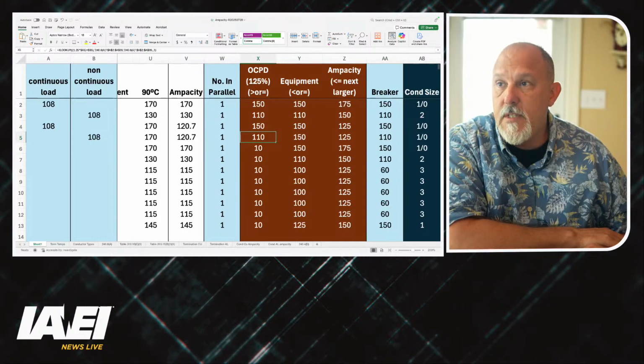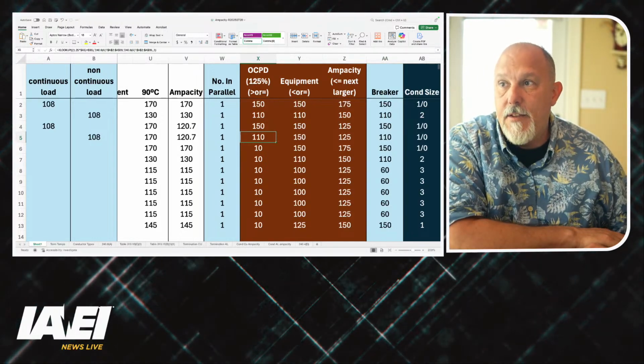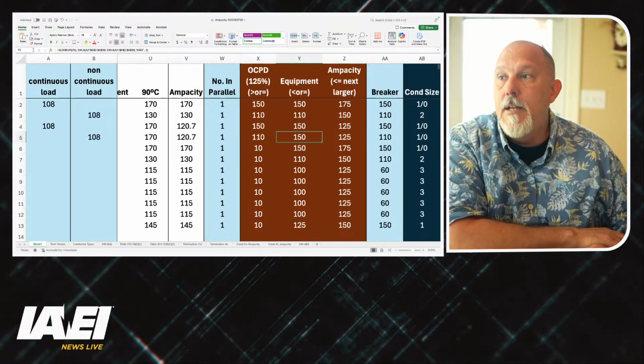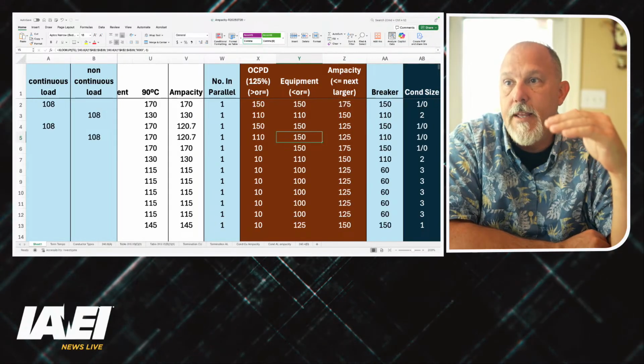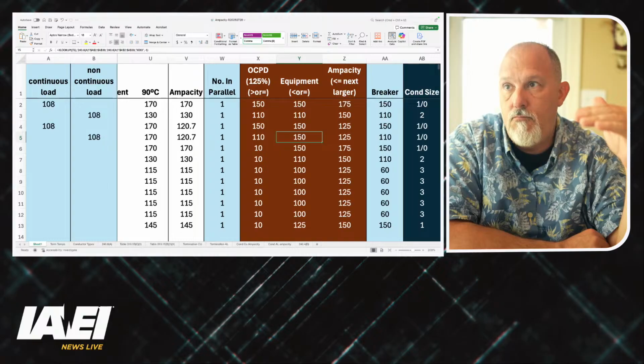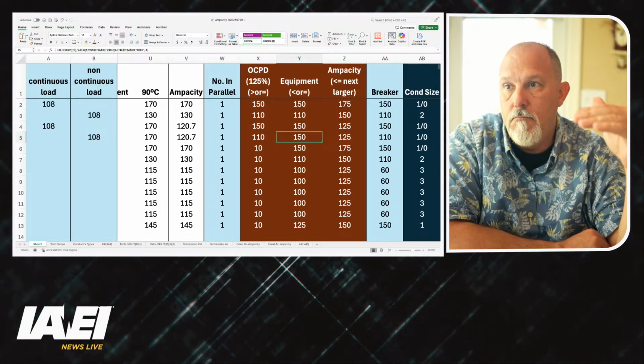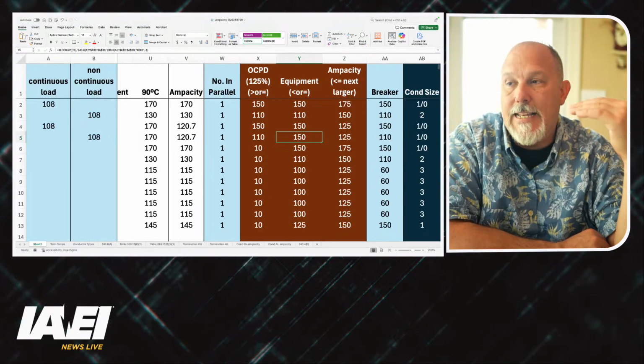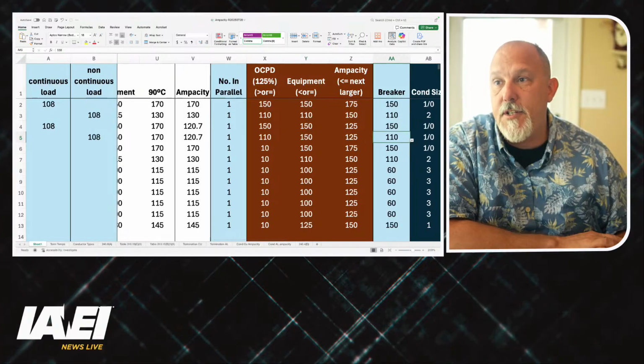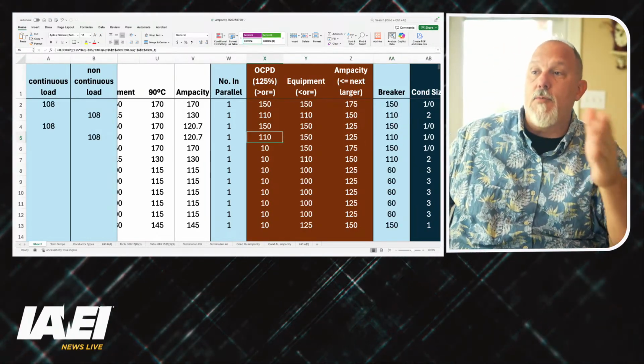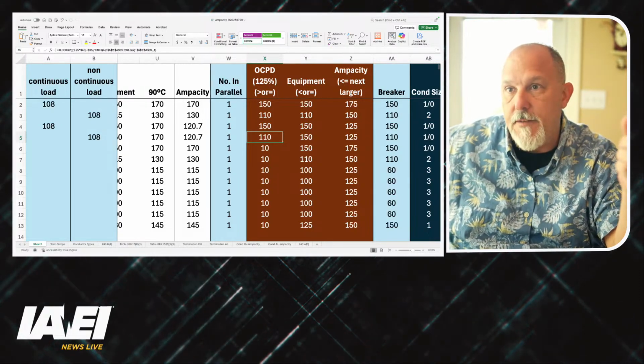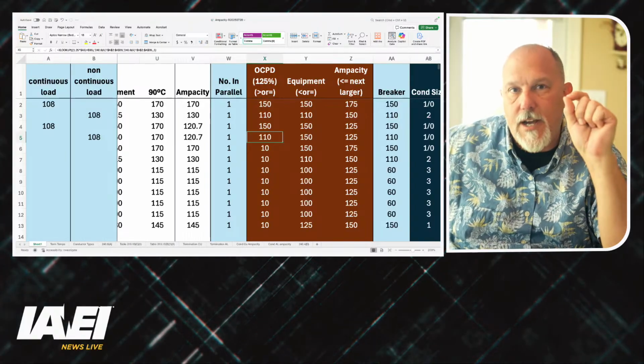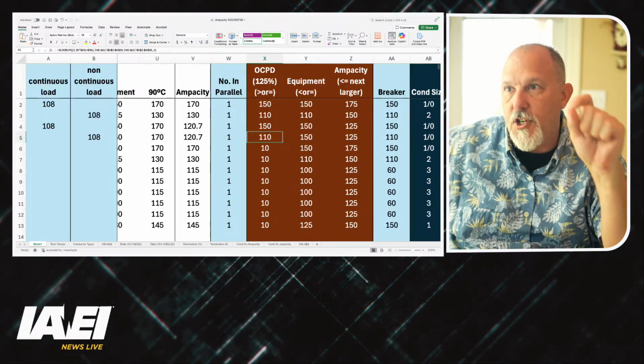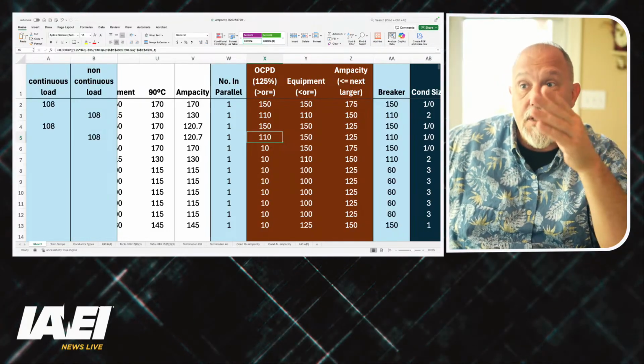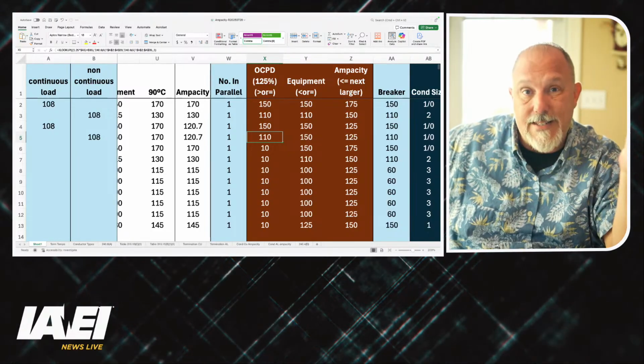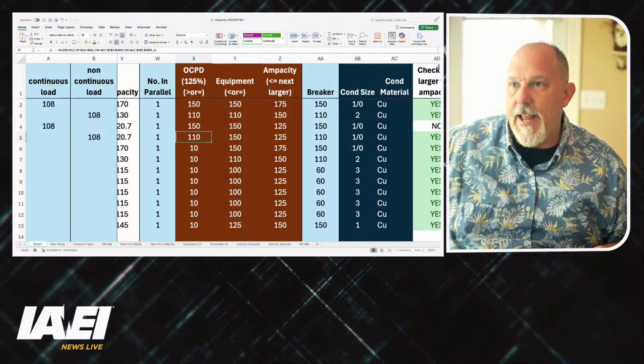For this one, a 110 amp breaker would satisfy the 125% rule, but because of the size of conductor and the ampacity, I can't be greater than. So I can pick a 110 amp breaker here too, because a 110 amp breaker would be greater than or equal to the 110 amps, which is the 125%. The 110 amp breaker would be less than or equal to the 150 amps worth of equipment for the termination. And the 110 amp breaker would protect the conductor at its ampacity because it's 120.7. So I'm going to say 110 amp.